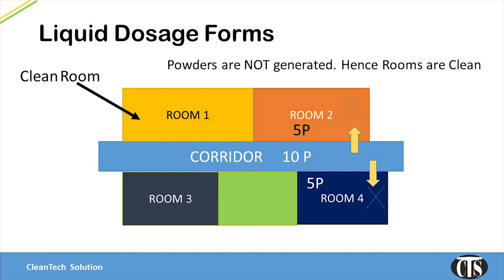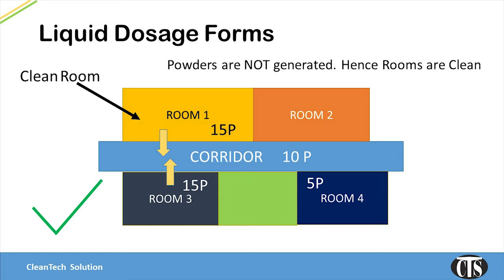Hence, if the corridor is kept at high pressure in a liquid manufacturing area, the dirty air of the corridor will go into the room when doors are open. So exactly the opposite of what is done in solid dosage form manufacturing is done here. The rooms are kept at higher pressure and the corridors are kept at lower pressure, so air from the room flows into the corridor.